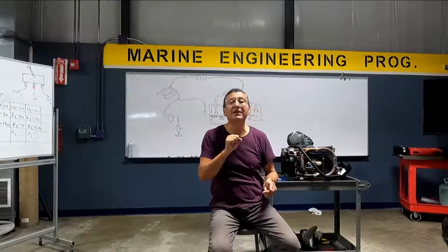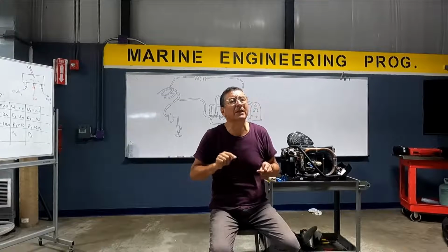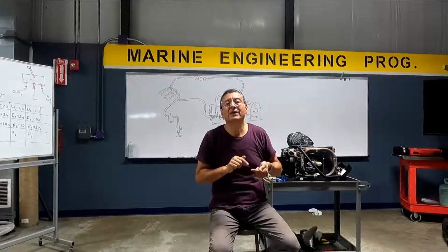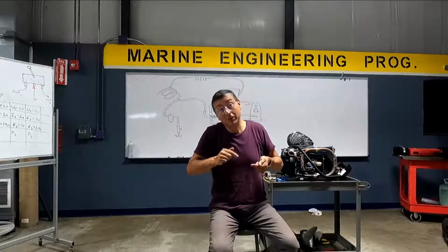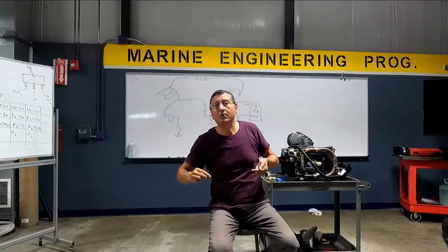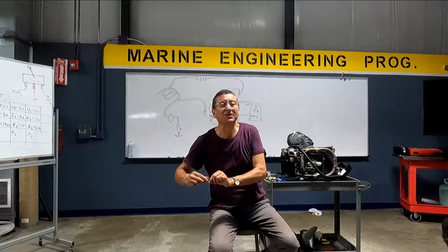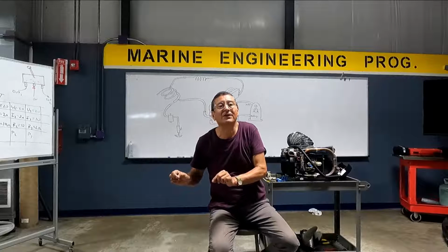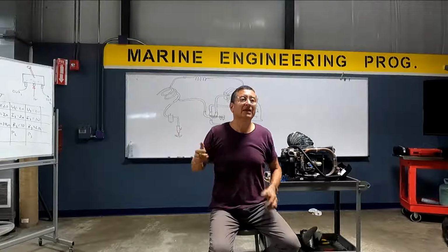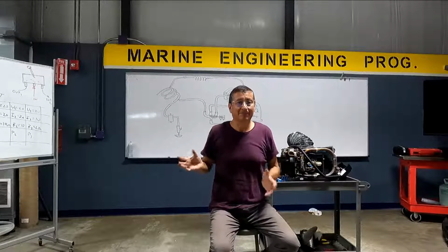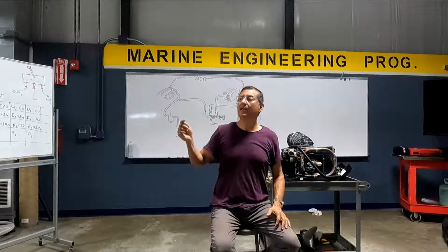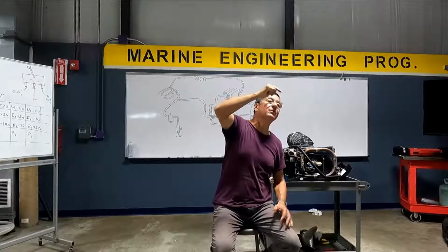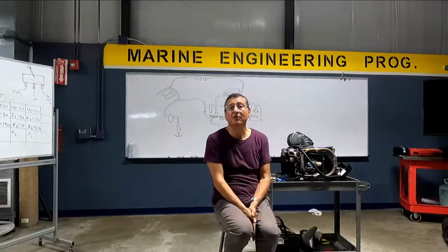And liquid enters the capillary pipe, or what is the other name for the capillary pipe? Expansion valve. When the refrigerant enters the capillary pipes, it enters liquid, high pressure, high temperature, passes through the capillaries, and at the output is liquid, but with low pressure and low temperature. It's practically frozen, but it's liquid, and enters the evaporator, and starts to evaporate. It starts to absorb heat, evaporate, and at the output of the evaporator the refrigerant is completely evaporated, and enters again in the compressor, vapor. That's the cycle. Good?